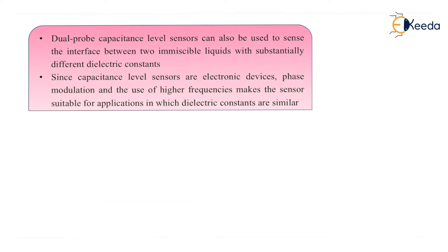In capacitance level measurement, dual probe capacitance level sensors can be used to sense the interface between two immiscible liquids with substantially different dielectric constants. Since these capacitance level sensors are electronic devices, phase modulation and the use of high frequencies make the sensor suitable for applications in which the dielectric constants are similar.